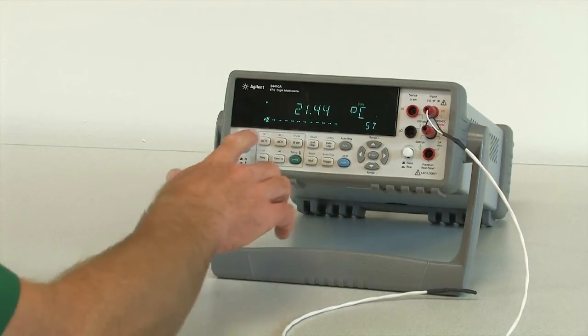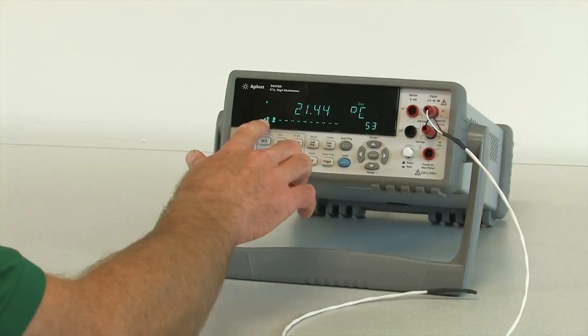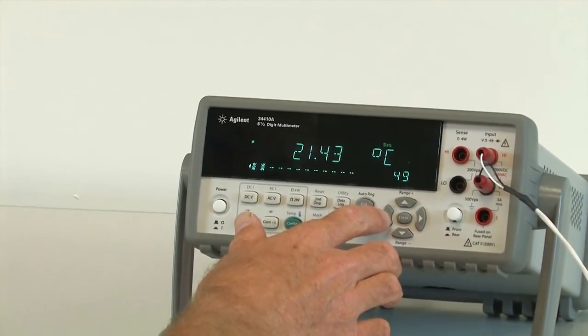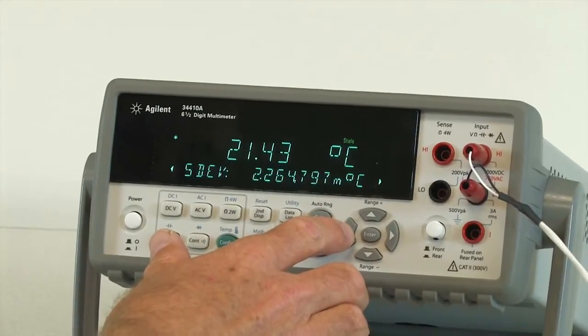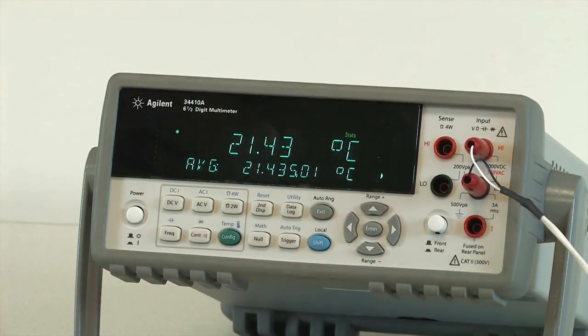So you can see the DMM, as it starts to complete, it counts down the number of readings left, and it has an indicator showing the progress. In addition, you can also go back to the math that we had enabled earlier, which is nice. You can get some idea of the readings as they're taking place to make sure that they make sense.